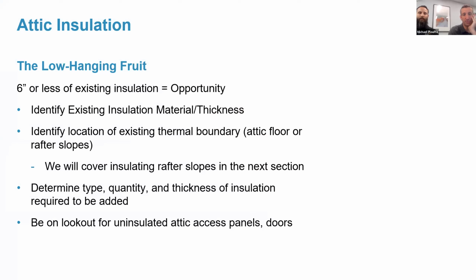We kind of refer to it as the low-hanging fruit. Buildings that were built 30, 40 or more years ago would have been insulated to code recommended levels at that time, which was based on energy prices from 40 or 50 years ago. Whereas nowadays, we'd recommend 12 to 14 inches as being an ideal level of attic insulation. So if at your facility, or the facility you're working at, or client you're assisting, you notice that there's 6 inches or less of insulation in an attic space, that generally means there's a good opportunity to improve upon that and yield some good cost-effective energy savings for the client.